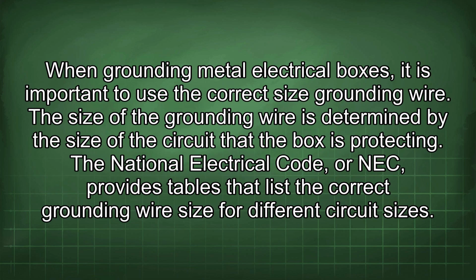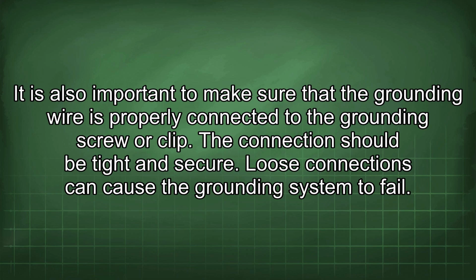When grounding metal electrical boxes, it is important to use the correct size grounding wire. The size of the grounding wire is determined by the size of the circuit that the box is protecting. The National Electrical Code, or NEC, provides tables that list the correct grounding wire size for different circuit sizes. It is also important to make sure that the grounding wire is properly connected to the grounding screw or clip. The connection should be tight and secure. Loose connections can cause the grounding system to fail.